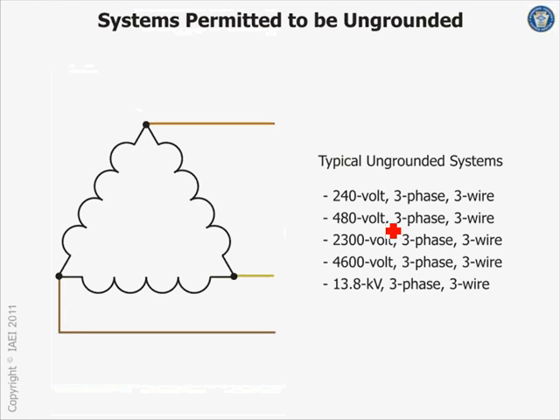These are the systems that you are allowed to bring to a building ungrounded by code. Do you see 208/120? It's coming from a Y. You can't bring 208/120 to a building ungrounded. 208/120, you cannot. Why? It's coming from a Y. If you bring up a Y, you ground it.